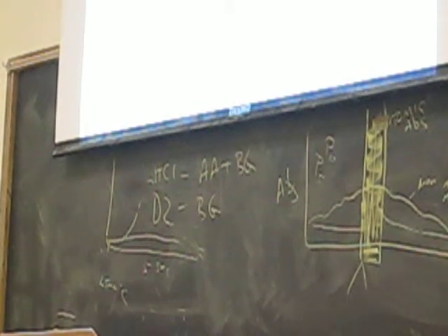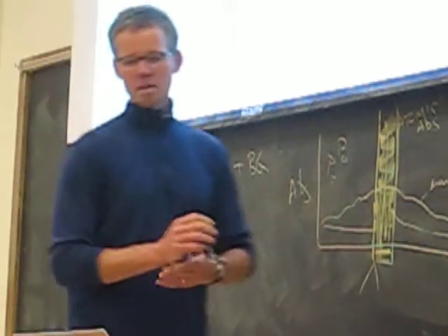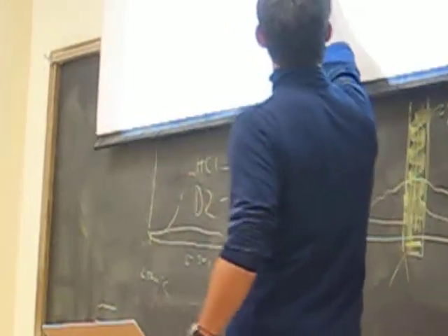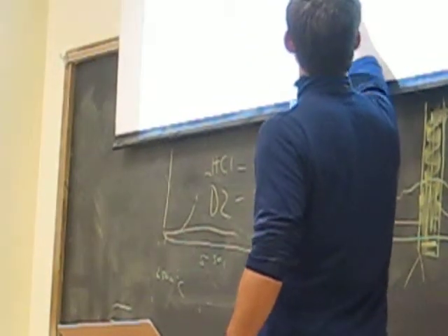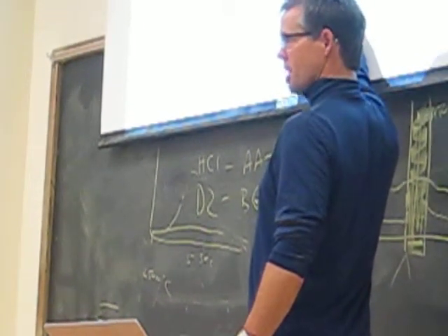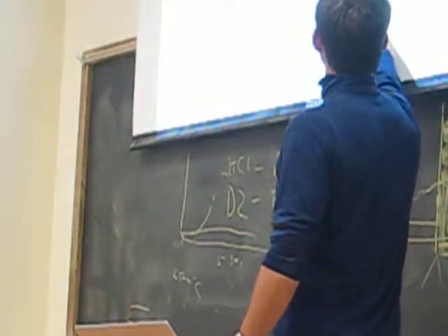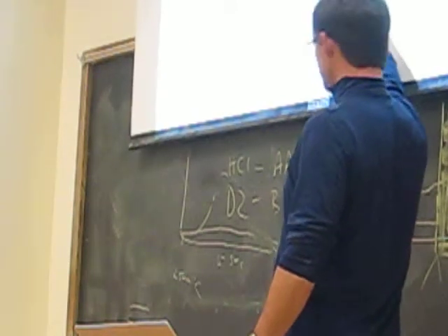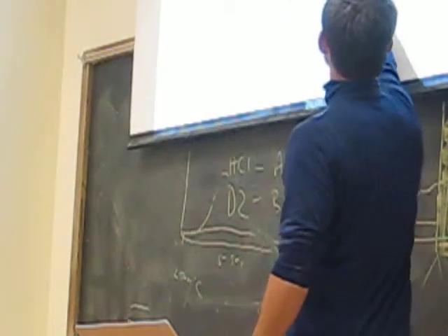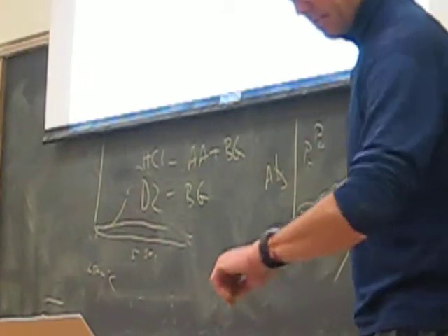Wouldn't the D2 arc lamp also capture some of the atomic absorption? It does. But the amount of absorbance of this broadband radiation from the D2 that is being absorbed by the copper, the very narrow atomic line, is extremely small. So it's no good for measuring atomic absorption, but it's perfect for measuring non-atomic absorption without being significantly interfered with by absorbance from the atomic absorption itself.